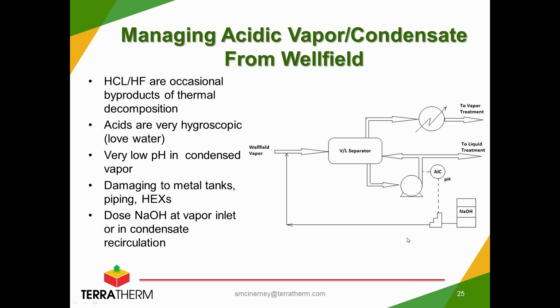So we often dose a caustic solution in through a spray nozzle into the well field vapor header as it flows into a vapor liquid separator, or similarly, we would just recirculate some caustic in the bottoms of this vapor liquid separator and make sure that we're neutralizing at the very front end of our system and not impacting our equipment downstream.